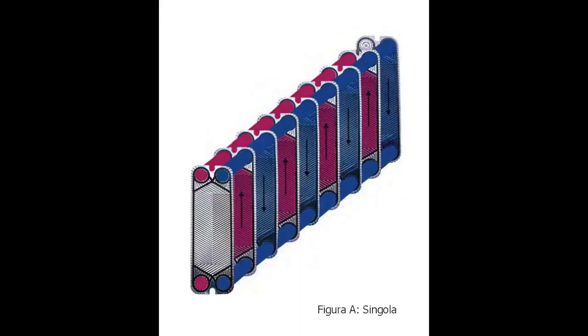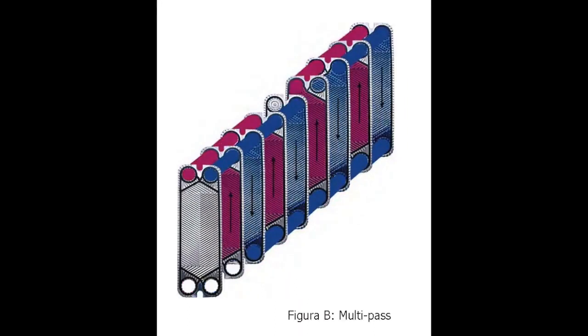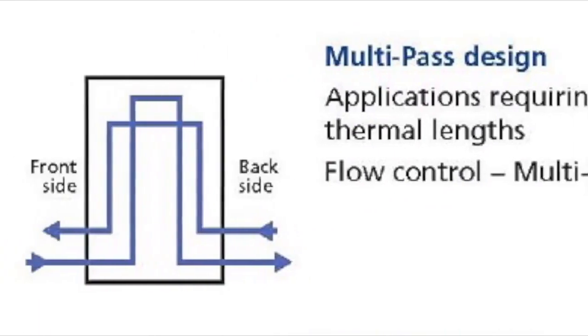What does it mean? Usually these exchangers have a particular plate arrangement inside, a scheme called multipass, meaning multiple passages. This type of multipass scheme is used when we require extremely long thermal jumps and extremely strong temperature crossovers, typically in recovery plants.